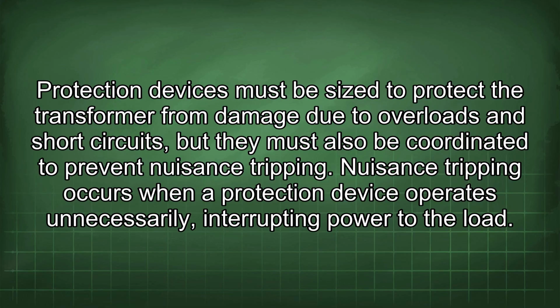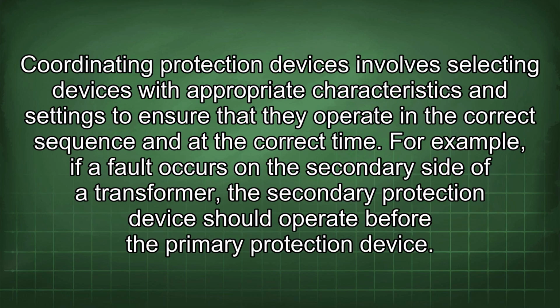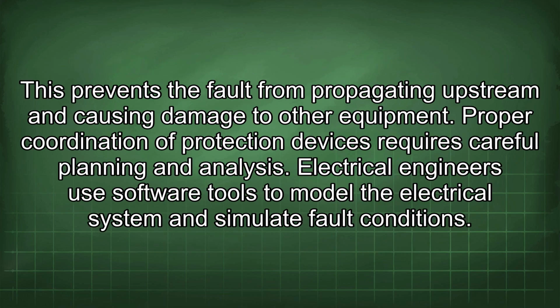Nuisance tripping occurs when a protection device operates unnecessarily, interrupting power to the load. Coordinating protection devices involves selecting devices with appropriate characteristics and settings to ensure that they operate in the correct sequence and at the correct time. For example, if a fault occurs on the secondary side of a transformer, the secondary protection device should operate before the primary protection device. This prevents the fault from propagating upstream and causing damage to other equipment.